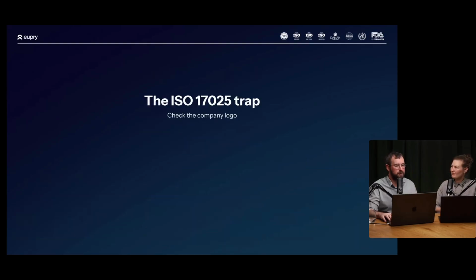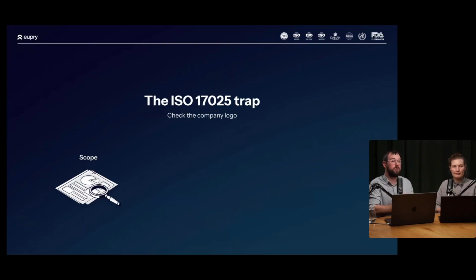I lied. I have just one more slide, then we'll go through all the questions. The last thing is the ISO 17025 trap, as we call it, where you just check the logo. A calibration laboratory can be accredited, but that does not mean they're accredited to calibrate exactly what you're asking for. That's what we call the scope. The scope of accreditation says this laboratory can calibrate between 0 and 100 degrees. They can still offer a minus 10 degrees calibration, but that will not be accredited. So you need to ensure the scope. Sometimes that's on their website, sometimes it's on the accreditation body's website.